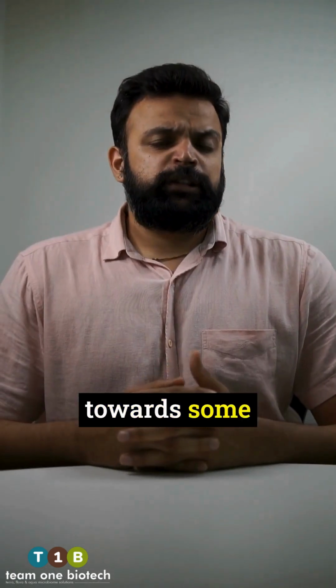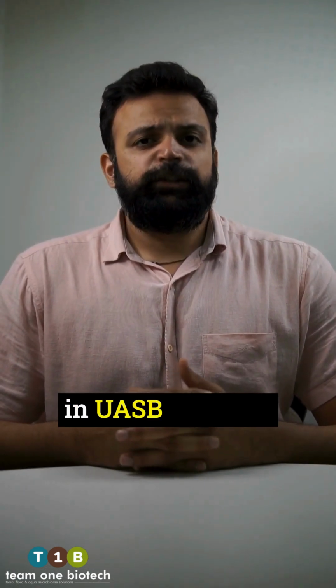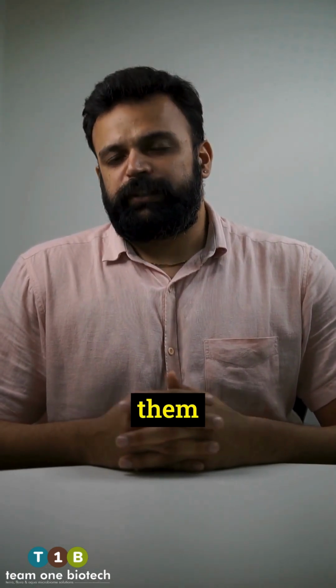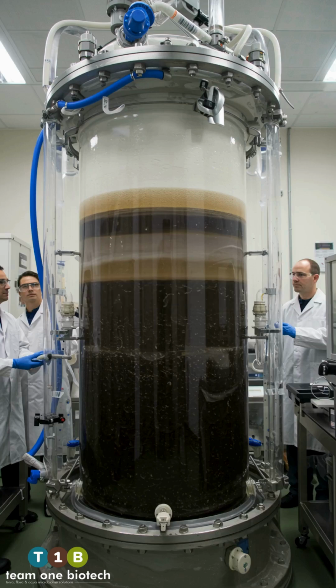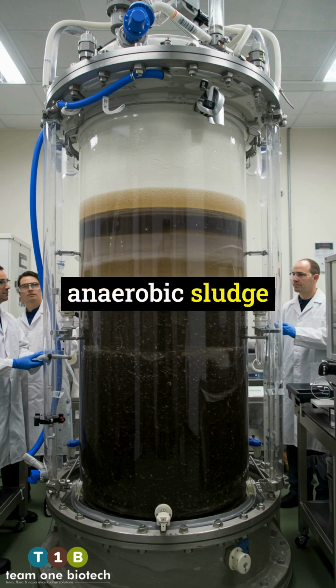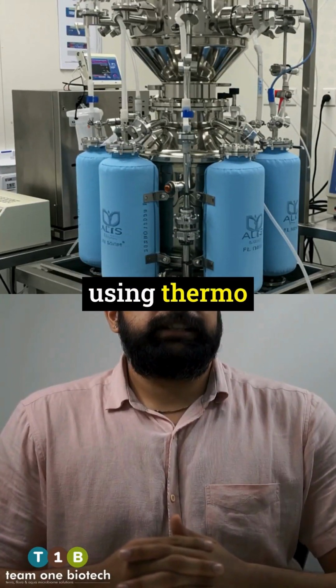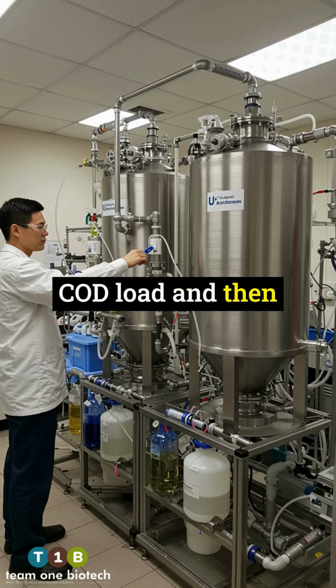Now we will move towards some of the common problems we face in UASB and how to troubleshoot them. First is long startup time. Seed with anaerobic sludge. Maintain temperature using thermal jackets and water bath. Start with low COD load and then gradually ramp up.